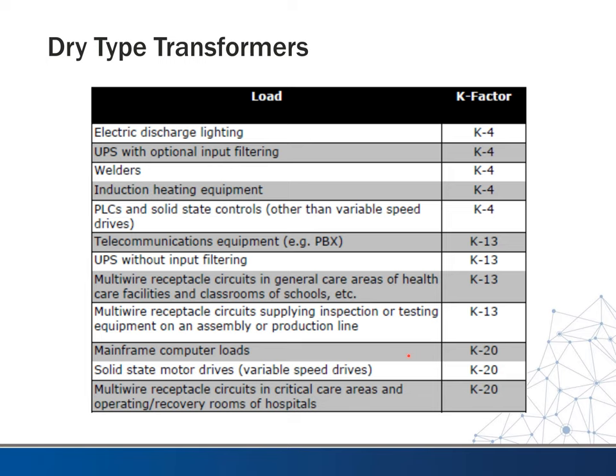You get down to mainframe computer loads, you don't see those a lot anymore, but if you run across one, you're probably going to want a K20. Solid state motor drives, if you have a bank of those, you might want to feed those through a K20. And things going into critical care and hospital rooms, K20, you don't want any noise coming back on those circuits there. So this is a pretty good rule of thumb table of when you might want to specify what type of transformer.